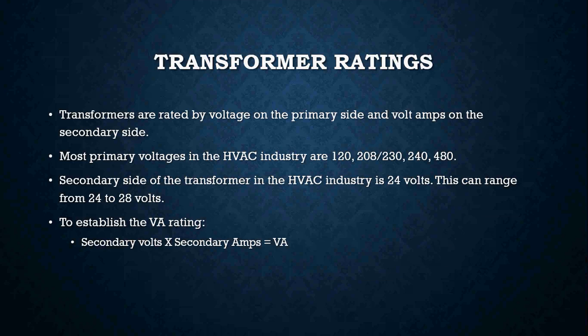The secondary side in the HVAC industry is most commonly 24 volts. When you take a voltage reading on a 24-volt transformer, it can range — this is perfectly normal. You're usually looking for a range anywhere between 24 and 28 volts. From my field experience, if you're not getting close to 24 volts, that can be a telltale sign that the secondary side of the transformer is starting to break down and will eventually fail.